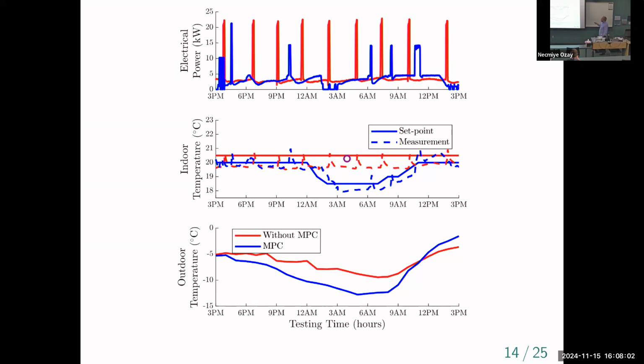And we're still getting those big spikes here, but actually we're running the heat pump a little bit colder overnight. And the reason for this is that we basically have a lower price for the thermal discomfort to the occupants in the overnight hours here. So this is basically between midnight and 9 a.m. So because of that, we don't get quite the same spikes for defrost usage. We don't get quite as much ice building up on the outdoor coil. So this effect of frost buildup was not at all on our radar when we started this problem, but it ended up being one of the dominant effects, both for this problem and for the next one that I'll discuss.